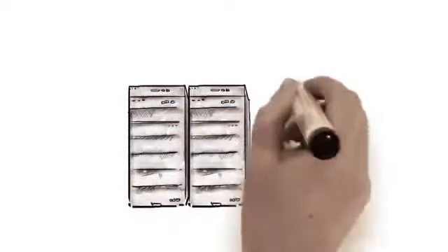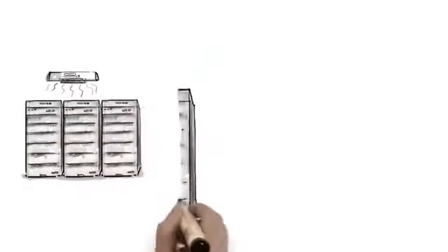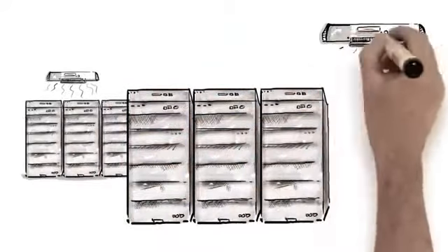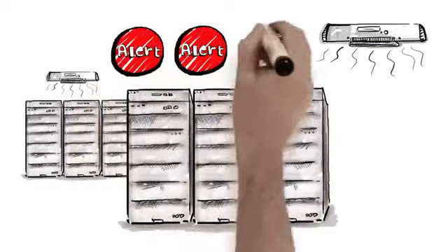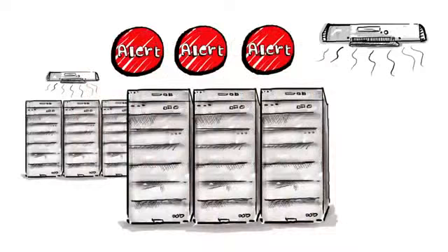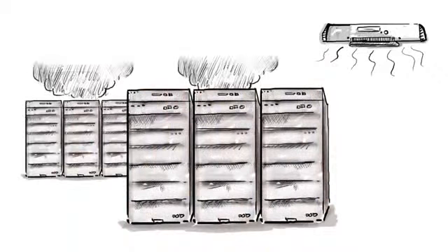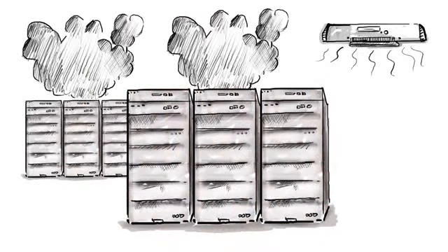Only doing ambient temperature monitoring isn't enough though. You could already face an earlier heat issue in your server racks that goes undetected as it is initially being compensated by the aircon. Only when the aircon can't cope anymore will you get alerted. At that point, it may already be too late for your equipment.